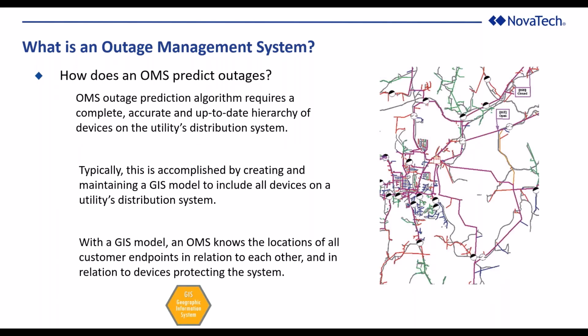So I mentioned that the OMS predicts outages - how does it do that? The OMS has an outage prediction algorithm, and for that algorithm to work properly it needs to know where meters are on the system, both in relation to other neighboring meters and in relation to protective devices - anything that will open or close the line, typically in response to an outage. That can be reclosers, breakers, and technically, for the purposes of the algorithm, even fused cutouts, though those typically aren't connected to SCADA.